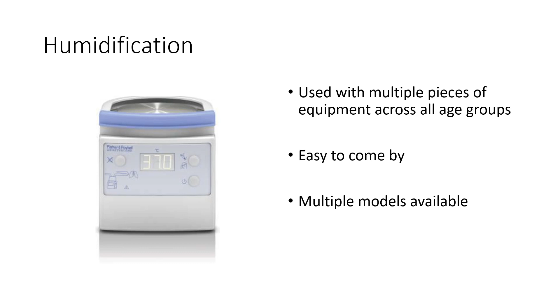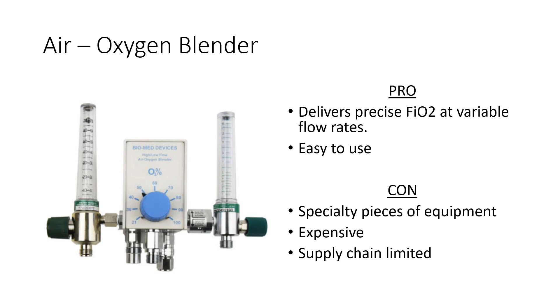The more gas, especially if you're bypassing the upper airway in any way or using very high flows, you should want that gas humidified. Next, the air oxygen blender for precise FiO2 delivery. If you work in a major medical center, you probably have plenty of these, but a lot of centers don't have that because they don't need to mix gas frequently, or they have ventilators that can mix the gas via an internal turbine. So it's a very precise specialty piece of equipment. It's expensive and it's supply chain limited right now. They're hard to come by.